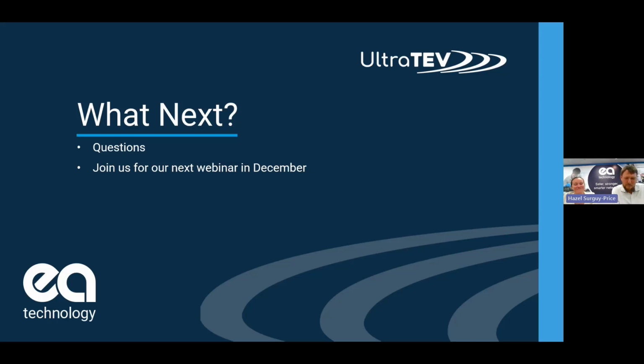It's going to be a long answer. The traditional accessories and measurement techniques we use are transient earth voltage, TEV—a plate built into the top of the device—and ultrasonics, also built into the device, with two or three accessories in that area. There are accessories to help you look at hard to reach places, so you can still see the screen over the top of switchgear, like the example we showed where we found a termination on the pole. That's done from an ultra dish, a parabolic dish that allows you to concentrate that energy over a long distance. There's also a device for looking inside sealed boxes where you haven't got an air path—that's the contact probe. So that's fairly traditional on the ultrasonic side.